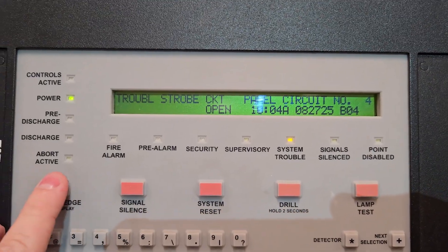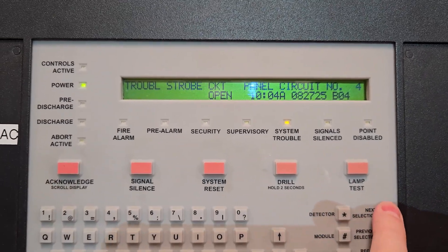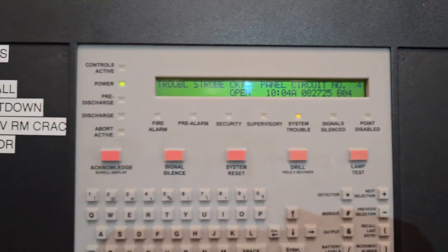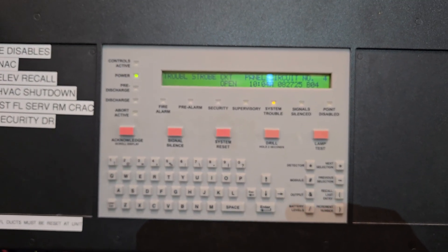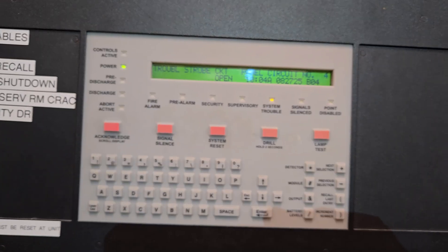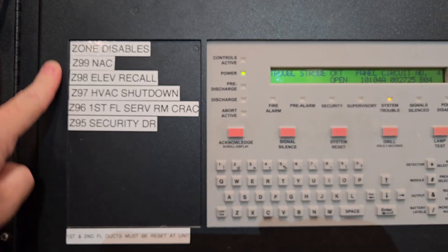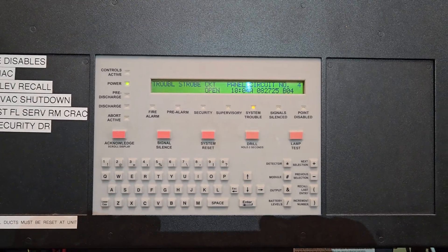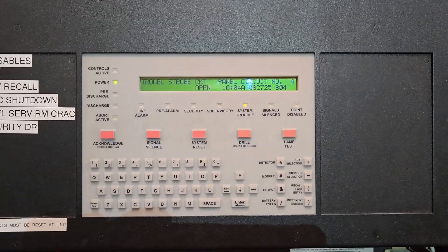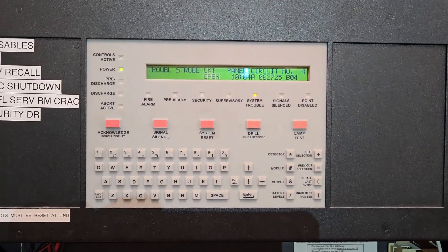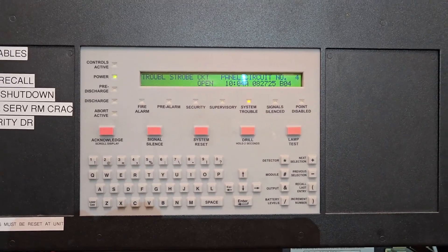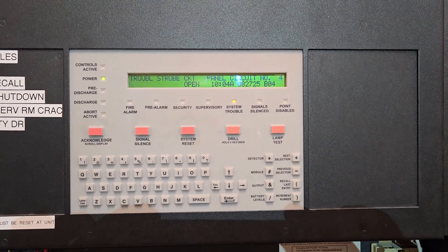I hit Escape to go all the way back out, and now I look at my troubles — I'm only going to have the one trouble I originally started with. I hit Enter and scroll with Next, and it's not showing me any additional issues. So that's how you go through the process of disabling and enabling. You can do it by zone, module, detector, or output. This panel is set up with zones, so I used zones. That is how you disable points and access the menu for the Notifier NFS-640 fire alarm panel.